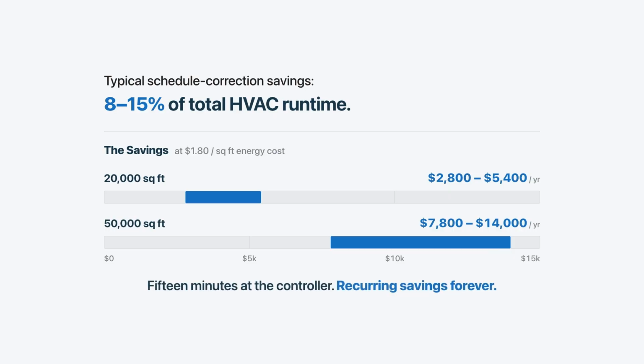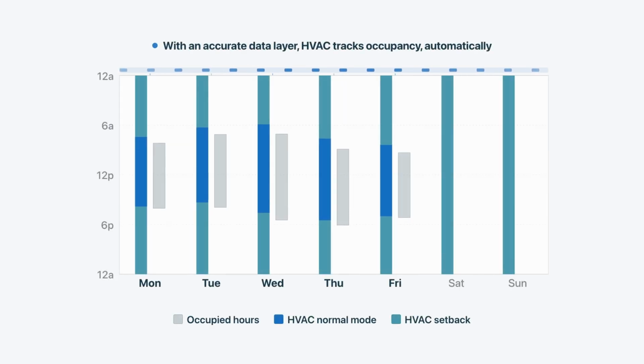These numbers compound because the energy savings recur every year the corrected schedule is maintained, which is why ongoing data matters. Schedules drift, building patterns change, buildings themselves change. A correction made once and never re-verified is always going to degrade over time. The data layer will always catch that drift and make the next correction easy. And that's the core difference between a one-time energy audit and continuous monitoring. The audit gets you a single correction. The monitoring makes every future correction cheap and on target.